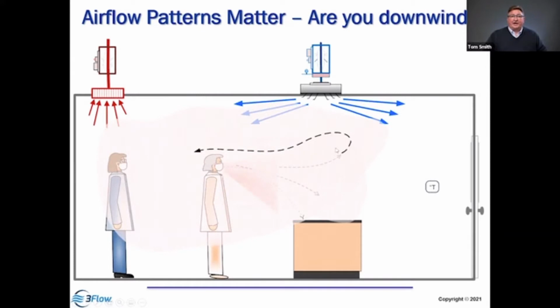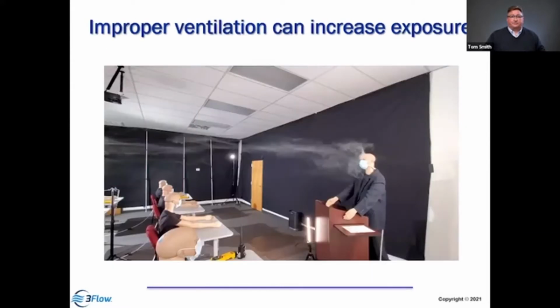If we look at the airflow patterns, it's possible that it's actually moving it back towards the healthy people. So looking at not only the volume of airflow, but the airflow patterns is very important. Here's an example. We use a lot of mannequins in our testing to simulate people, and we're going to cover that in detail as we start talking about fume hoods. But we took our mannequins and hooked them up to a smoke source, and then we can use this to show what happens as people exhale and what the airflow patterns are doing to the effluent migration.